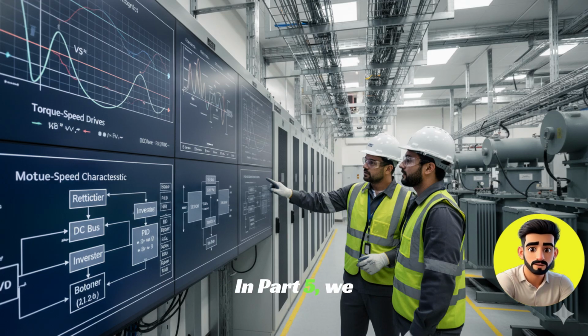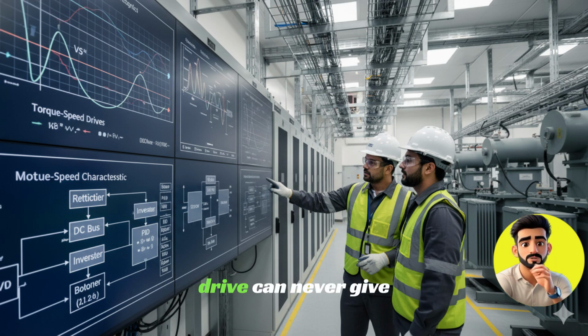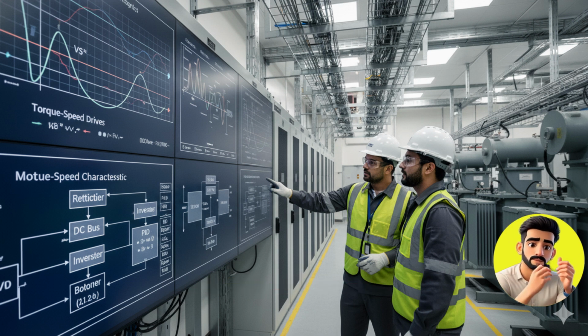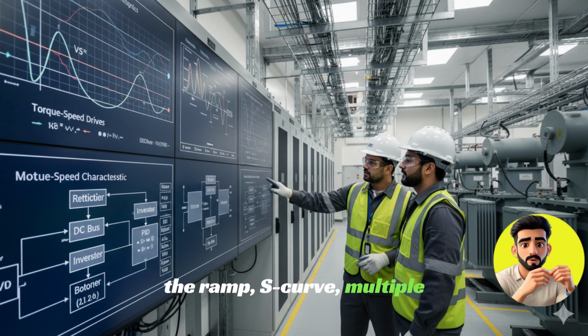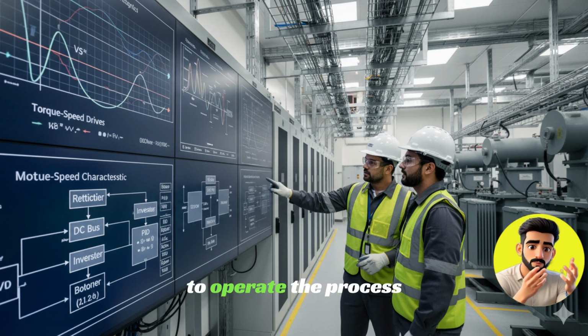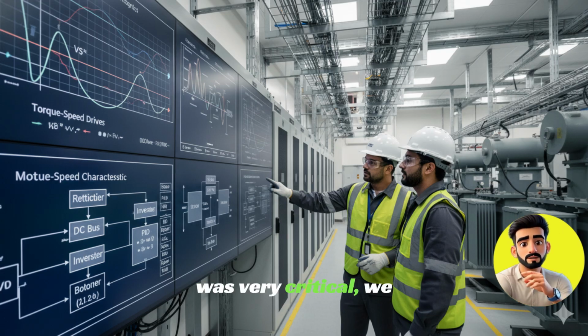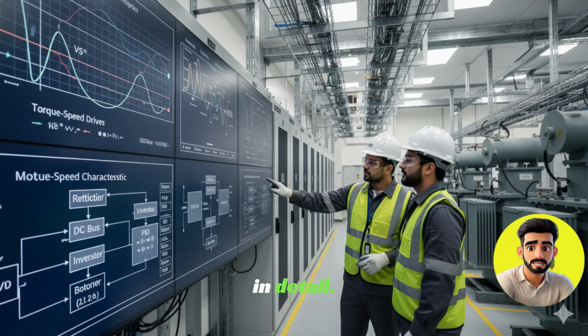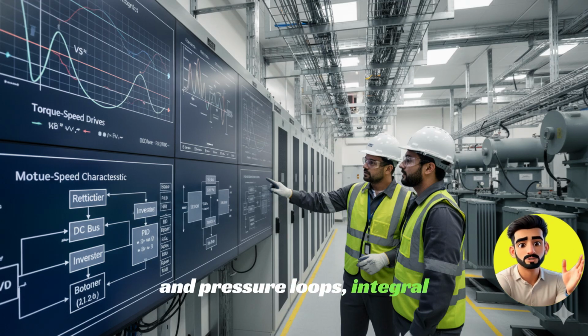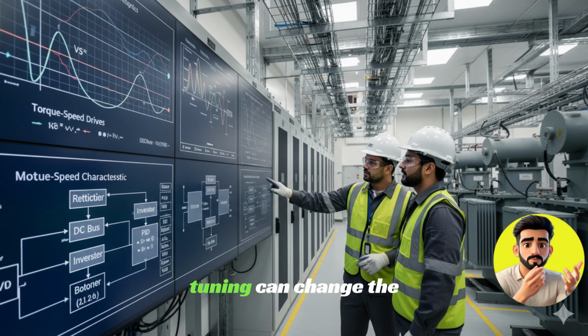In part 5, we saw that if motor parameters or auto-tune are not correct, then the drive can never give its full performance. In part 6, we learned how to use the ramp, S-curve, multiple speeds and jog functions to operate the process smoothly. In part 7, which was very critical, we broke down the PID in detail. Step response tuning, settings of pump, fan, level, and pressure loops, integral windup, and how proper tuning can change the behavior of the entire plant.